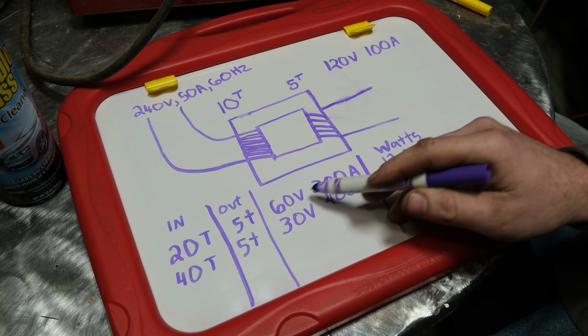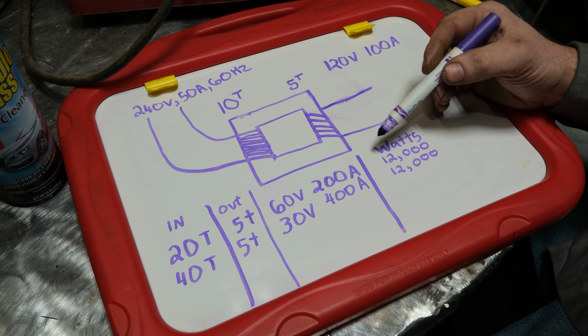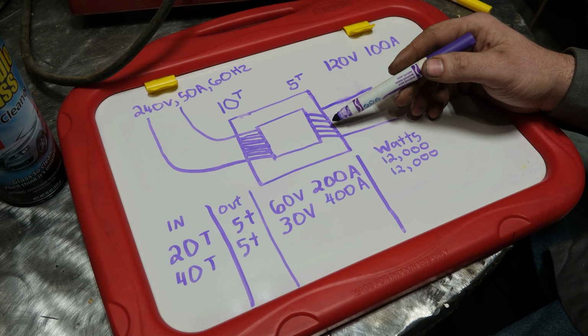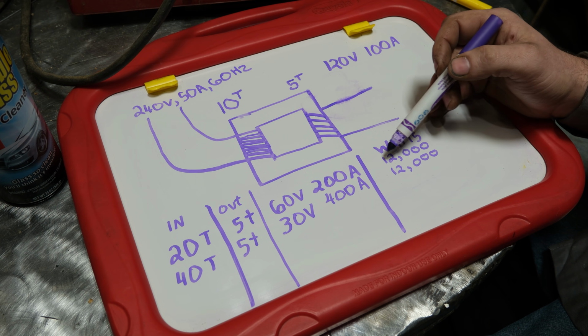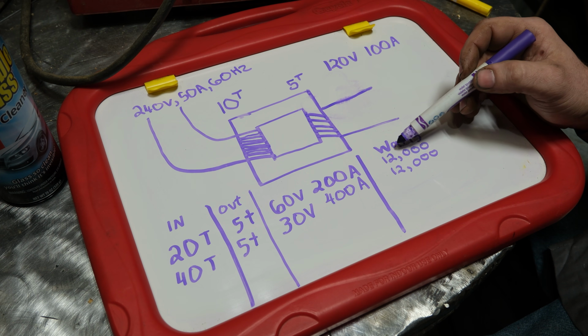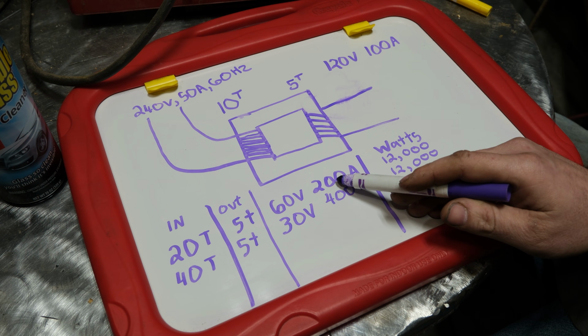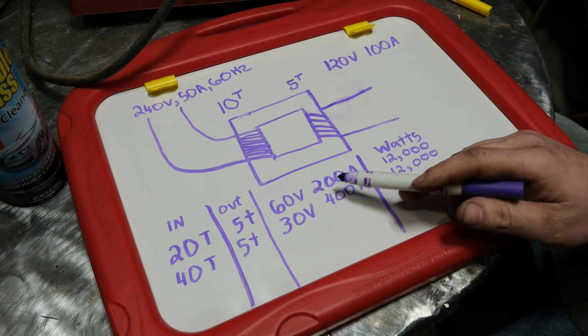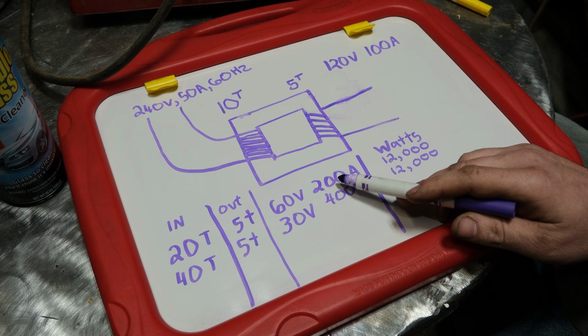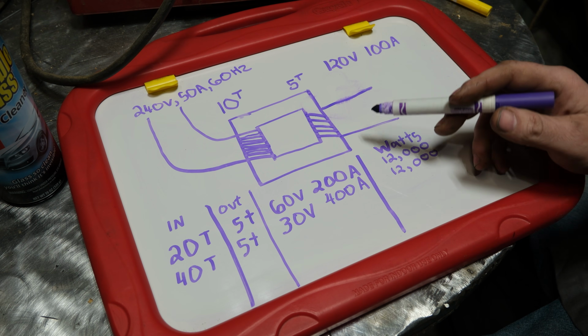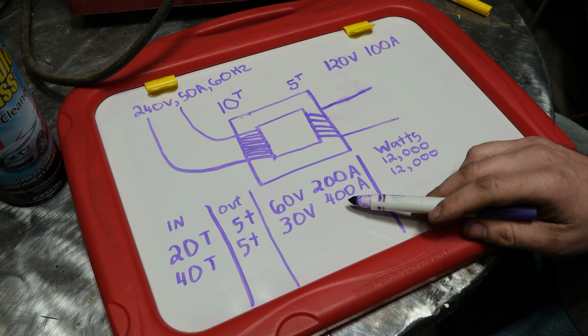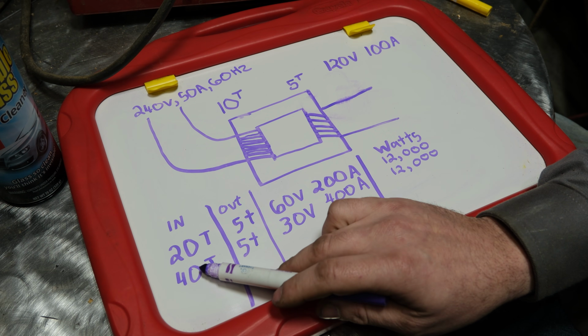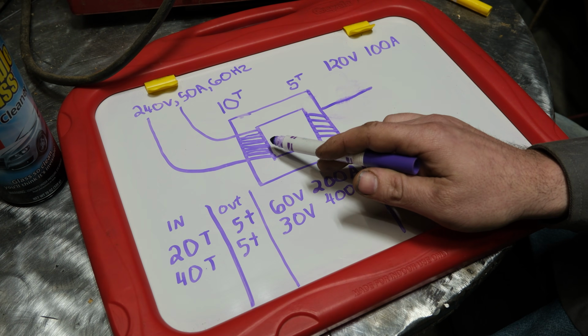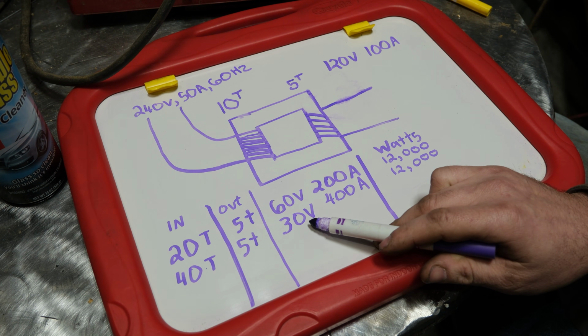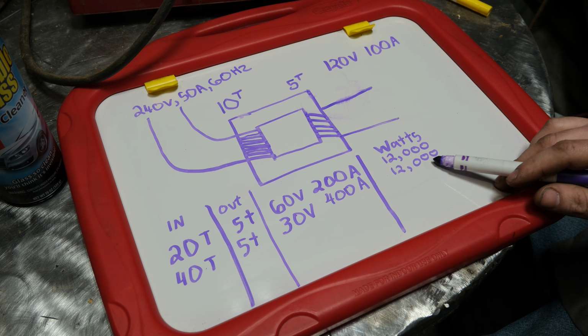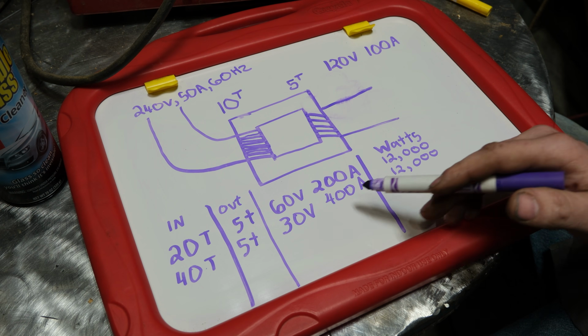Now, as you notice, again, this is still 12,000 watts. In the real world, you will never achieve 100% efficiency through a transformer, especially at lower frequency of input power. So this is closer to like 6,000 or 7,000 watts of output, and we would not achieve these numbers. A realistic number on a 20 turn to 5 turn would probably be closer to something like 40, 50 volts under load at most, and probably 140 amps, somewhere in that ballpark. So the efficiency brings everything down. Now, to make it even higher amperage and lower voltage, if we went 40 wraps of wire on the input and 5 on the output, we could get to 30 volts and 400 amps. Again, same 12,000 watts, but again, efficiency, we would be well under that.